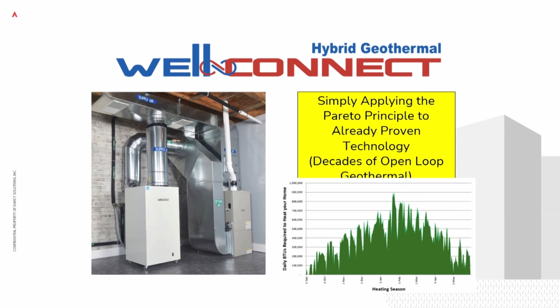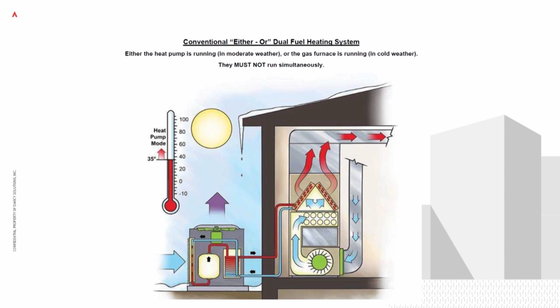We also looked at most dual fuel systems, where when the heat pump can't keep up, you shut it off and the furnace, the supplemental heat, turns on and does everything. So what we did, instead of an either-or, we did an and. We installed a damper over the furnace and a damper over our geothermal heat pump, allowing both systems to operate simultaneously. The benefit is that over the course of the winter, even on the coldest days of the year, you're still getting your full 400% efficiency out of the ground energy, while the furnace just turns on to supplement and get the house to temperature if needed.